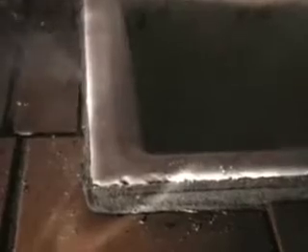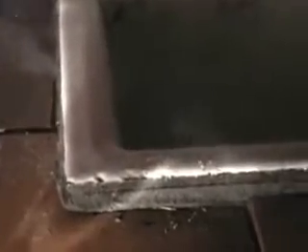We pressurized the lines with smoke and, lo and behold, we've got smoke pouring out of the ground on the outside edge of this floor sink, clearly showing that there's deteriorated pipe in the ground right in this area. And it's allowing sewer gas to leak into the building right here at this point.